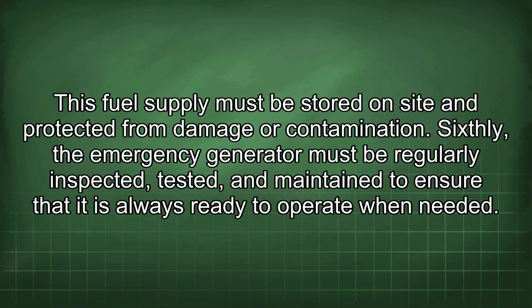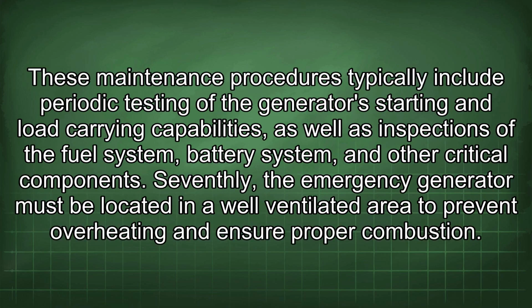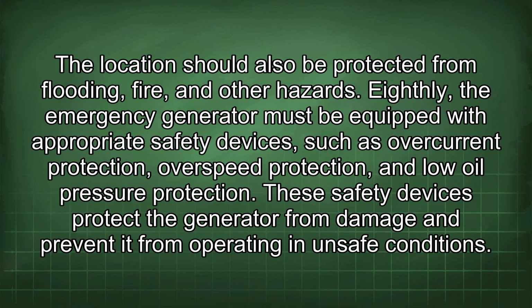Sixthly, the emergency generator must be regularly inspected, tested, and maintained to ensure that it is always ready to operate when needed. These maintenance procedures typically include periodic testing of the generator's starting and load carrying capabilities, as well as inspections of the fuel system, battery system, and other critical components. Seventhly, the emergency generator must be located in a well-ventilated area to prevent overheating and ensure proper combustion. The location should also be protected from flooding, fire, and other hazards.